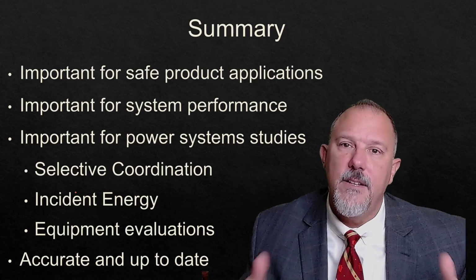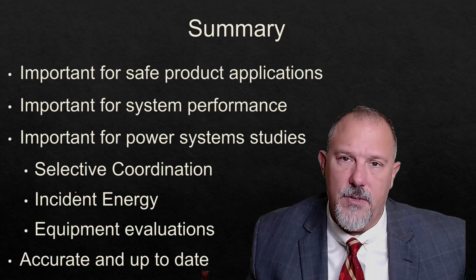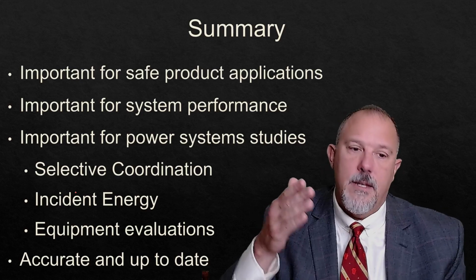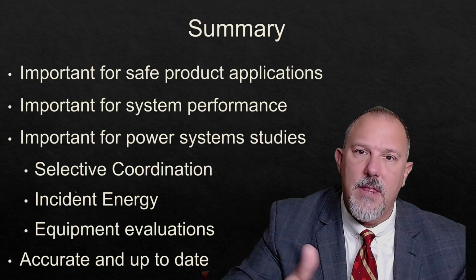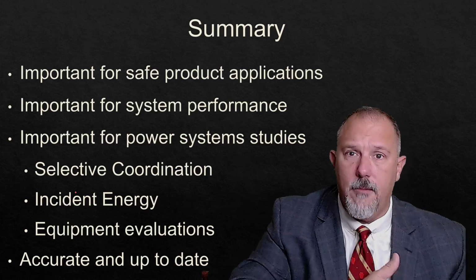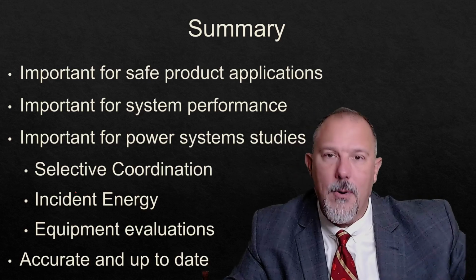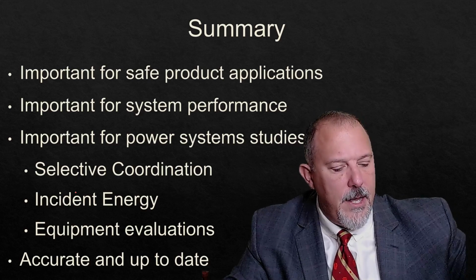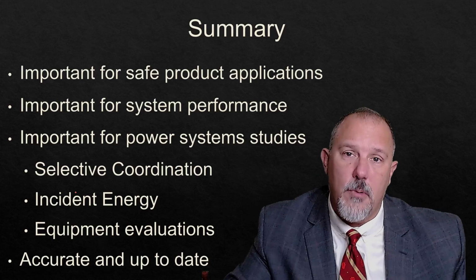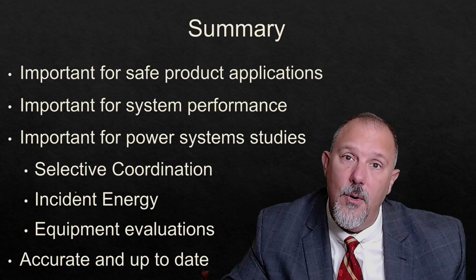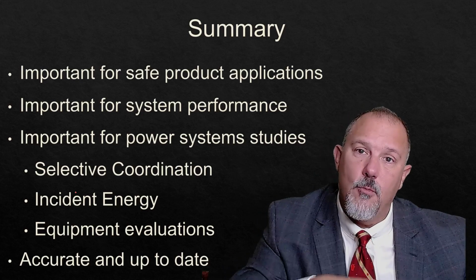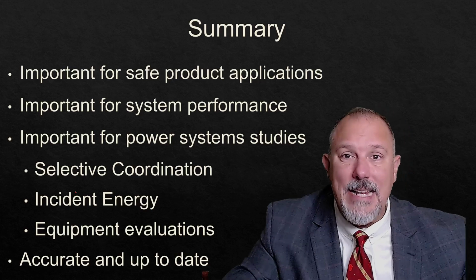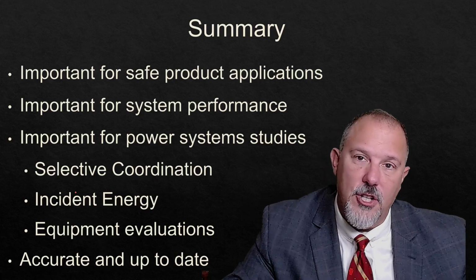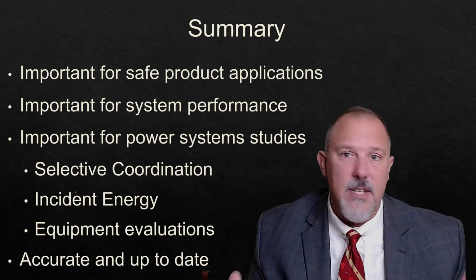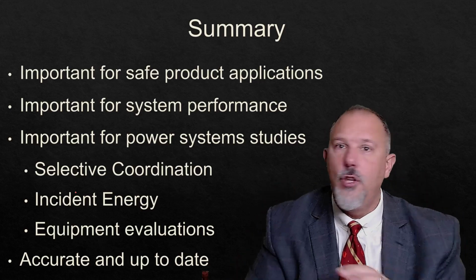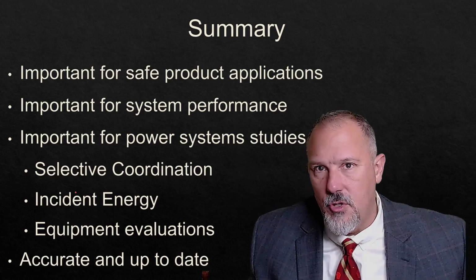If I'm going to selectively coordinate my system, I need to know my fault currents. If I want to make sure that I achieve 100,000 or 200,000 amp short circuit current ratings, I need to know I have the right proper interrupting ratings and the right overcurrent devices to relieve those pressures of fault currents. I need to know that my ratings of my equipment exceed the available fault current at any one of those locations. And remember, just putting a 200,000 amp fuse at the main does not mean you don't have to worry about fault current throughout the entire distribution system.